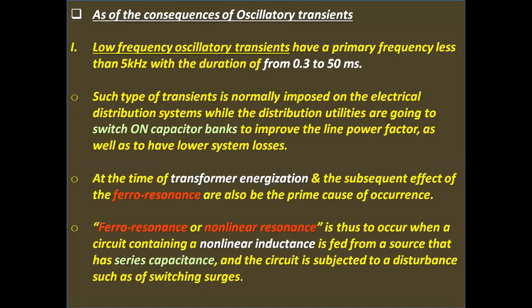As for the consequences of oscillatory transients, low frequency oscillatory transients have a primary frequency less than 5 kilohertz with the duration of from 0.3 to 50 milliseconds. Such transients are normally imposed on electrical distribution systems while the distribution utilities switch on capacitor banks to improve their line power factor as well as to have lower system losses. At the time of transformer energization, the subsequent effect of ferroresonance can also be the prime cause of occurrence of low frequency oscillatory transients.